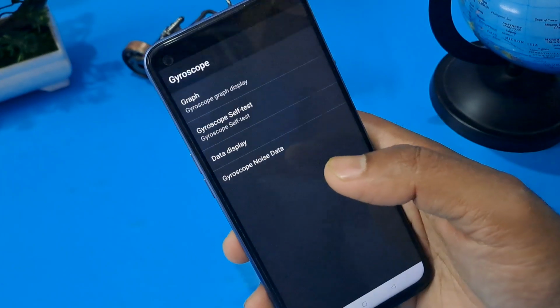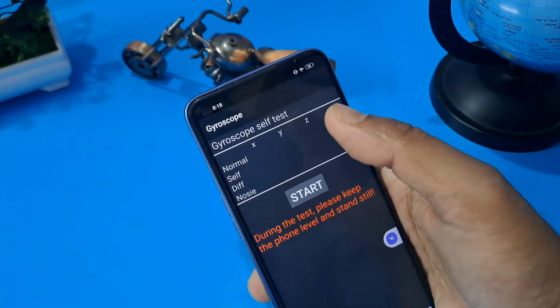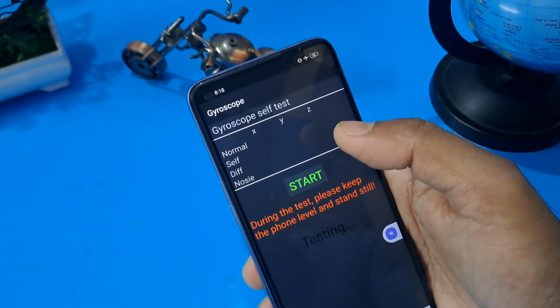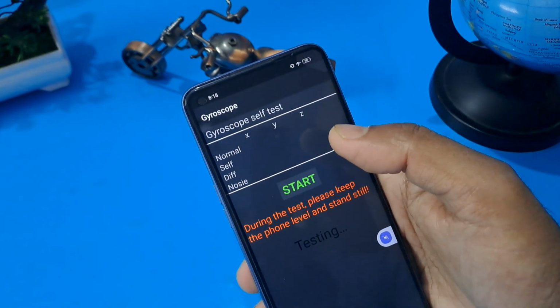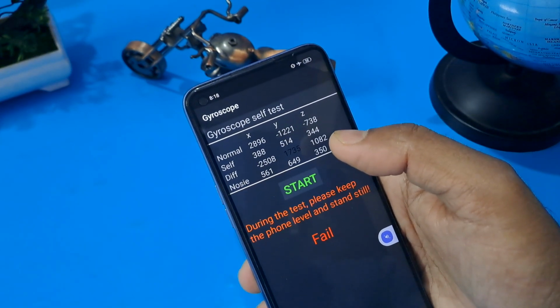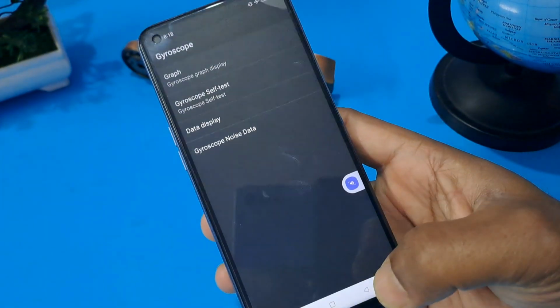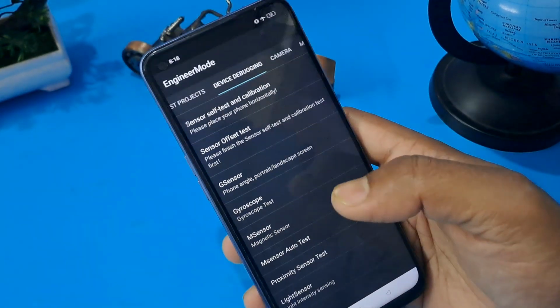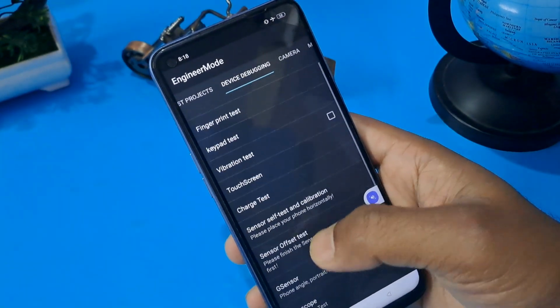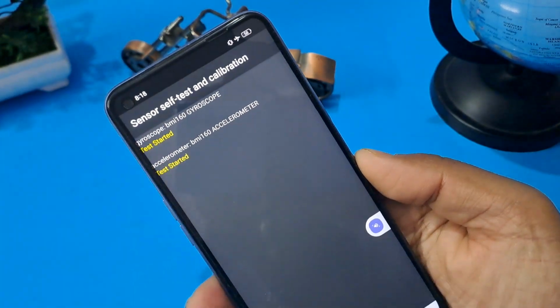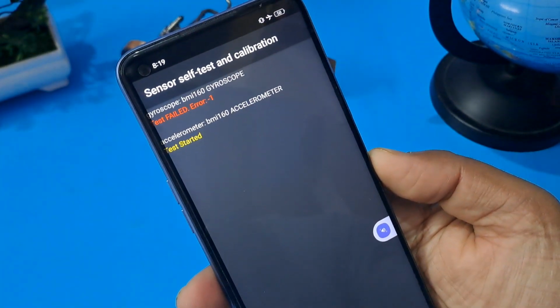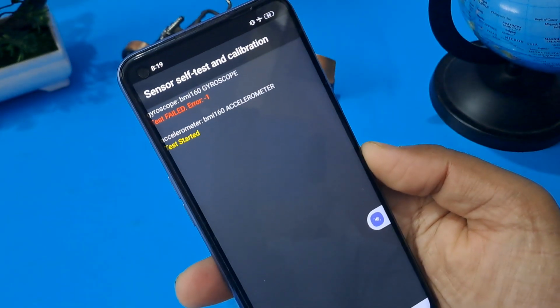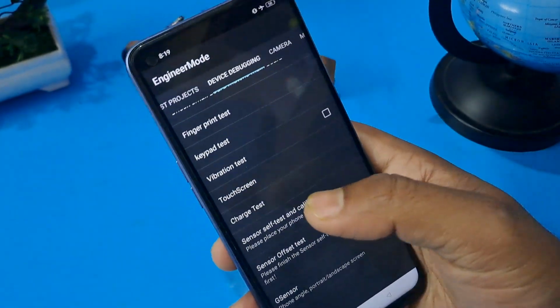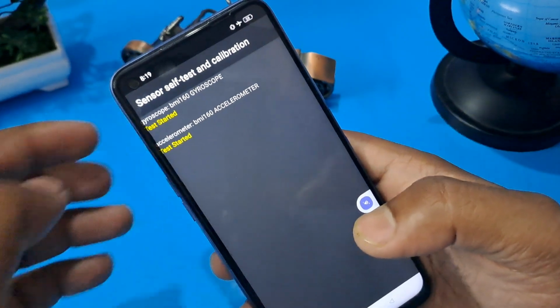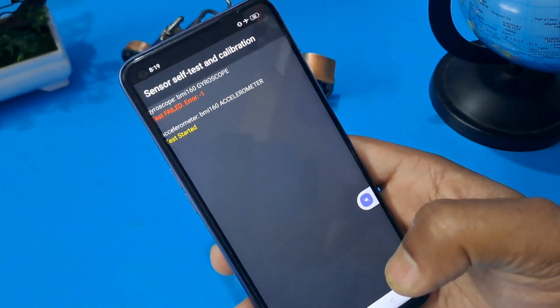Again we have to check the gyroscope. Start the gyroscope self test and check if XYZ is working or not. XYZ is working, so come back from this option, and now check the sensor self test calibration. You can see both options are not operated; gyroscope and accelerometer, at least one of each we have to pass. So apply this process till it's passed.